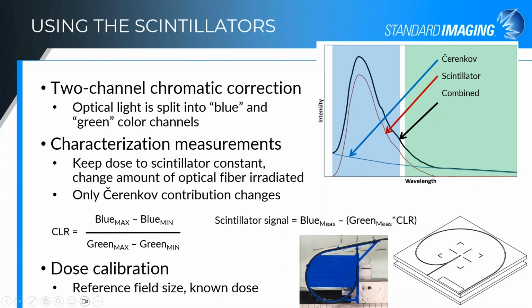The point, again, as I mentioned, is not to change the dose to the tip of the fiber. The W1 comes with this calibration slab or characterization slab and has a milled out channel for that minimum fiber configuration and then for the maximum fiber configuration. This is an option with the W2 as well if you would rather have the solid slabs in addition to just the water tank jig, or you can do your measurements in the water tank.